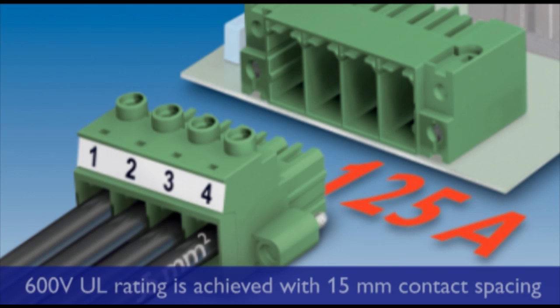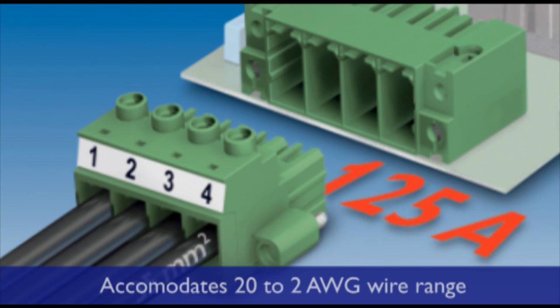A 600 volt UL rating is achieved with the 15 millimeter contact spacing. The PC35 will accommodate a wire range of 20 to 2 AWG.